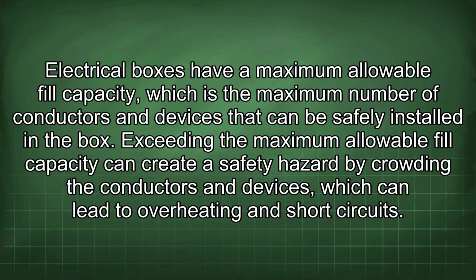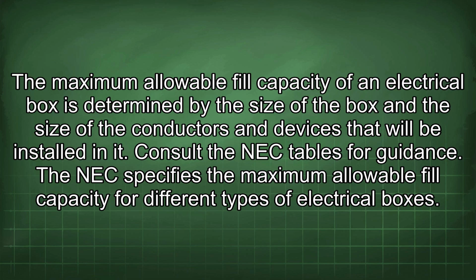Electrical boxes have a maximum allowable fill capacity, which is the maximum number of conductors and devices that can be safely installed in the box. Exceeding the maximum allowable fill capacity can create a safety hazard by crowding the conductors and devices, which can lead to overheating and short circuits. The maximum allowable fill capacity of an electrical box is determined by the size of the box and the size of the conductors and devices that will be installed in it. Consult the NEC tables for guidance. The NEC specifies the maximum allowable fill capacity for different types of electrical boxes.